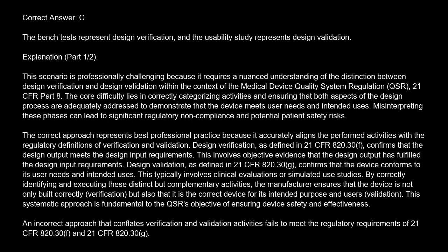This involves objective evidence that the design output has fulfilled the design input requirements. Design validation, as defined in 21 CFR 820.30(g), confirms that the device conforms to its user needs and intended uses. This typically involves clinical evaluations or simulated use studies.